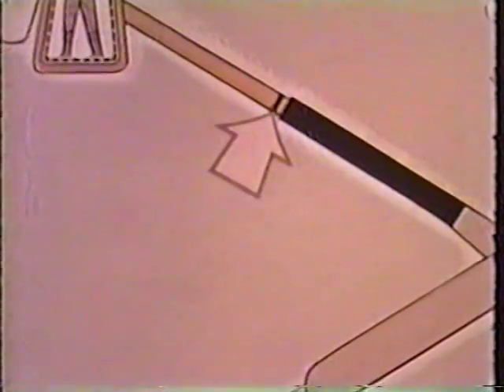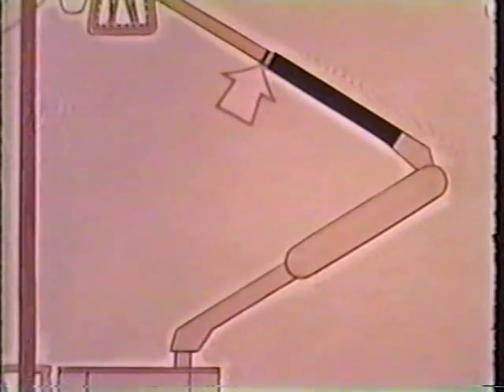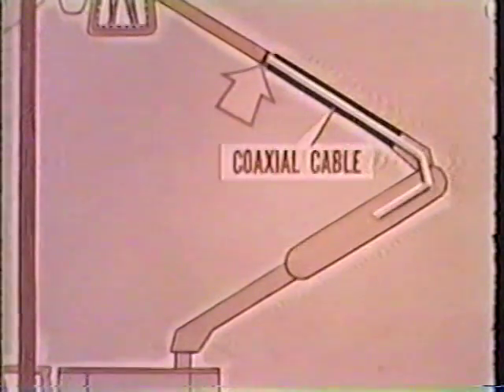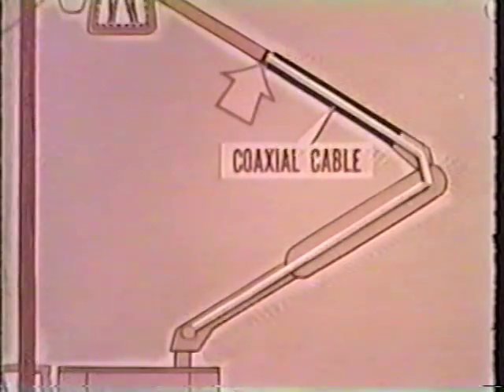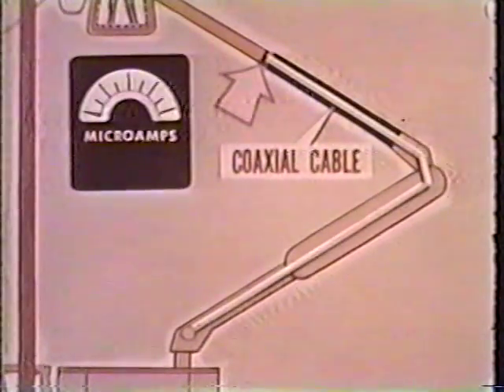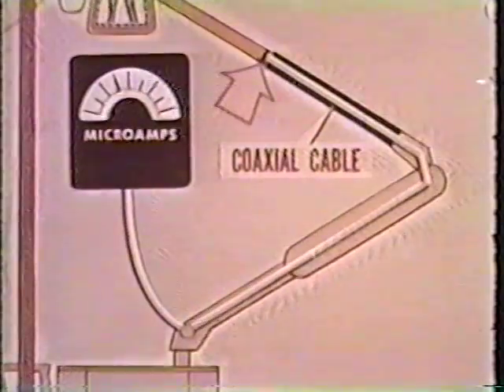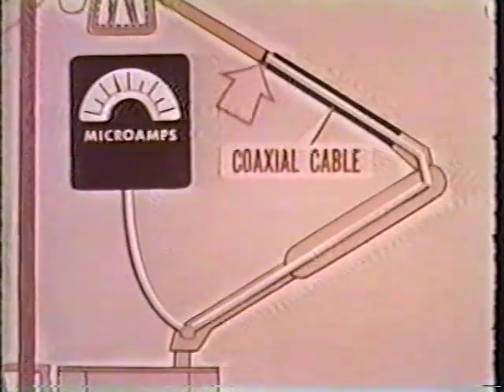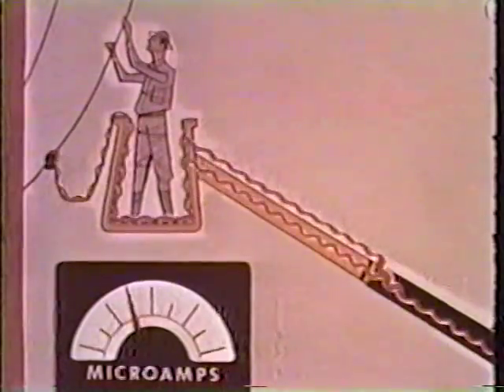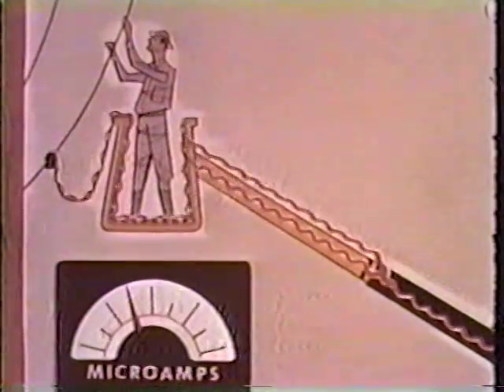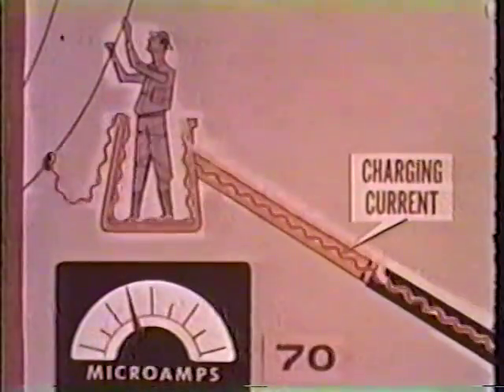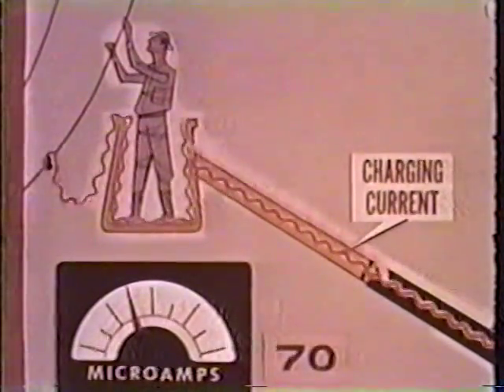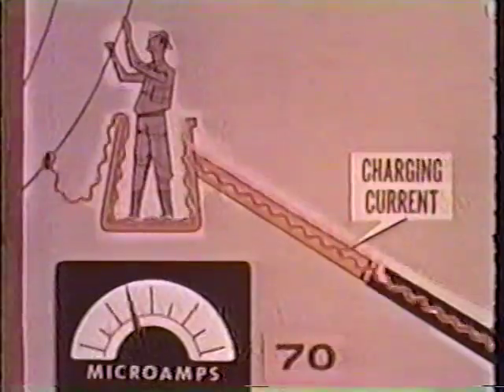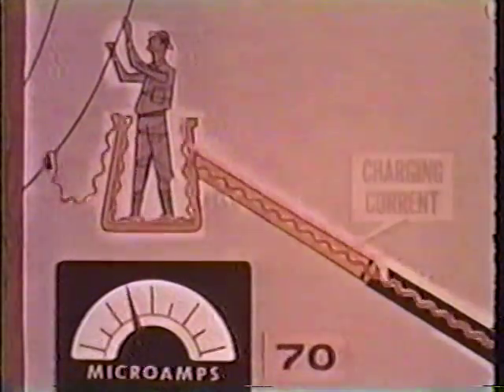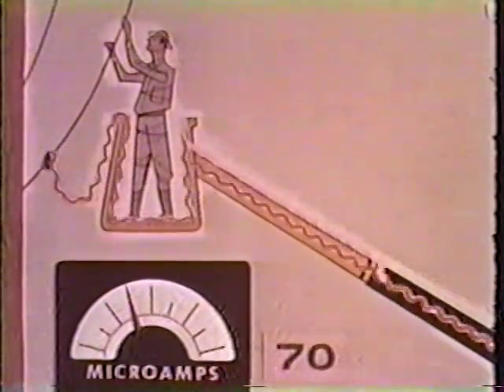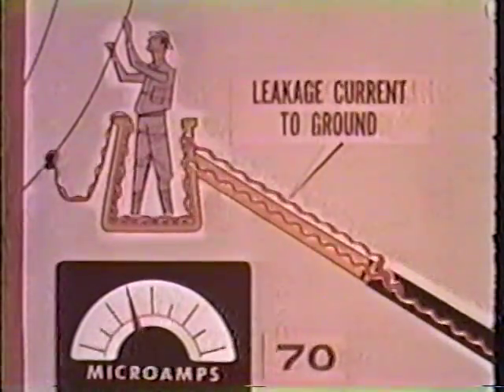Arm current is collected by a built-in electrode at the lower end of the fiberglass arm and carried by a coaxial cable to an outlet at the base of the lower arm. A meter, available from Holland, plugs into the outlet and measures the arm current in microamperes. Of the two components making up the arm current, the charging current represents a nominal 70 microamperes on the 55-foot Holland unit when performing work at its rated voltage of 138 kV. The second component, which makes up the arm current, is leakage, which passes over the arm because of contamination on its surface.